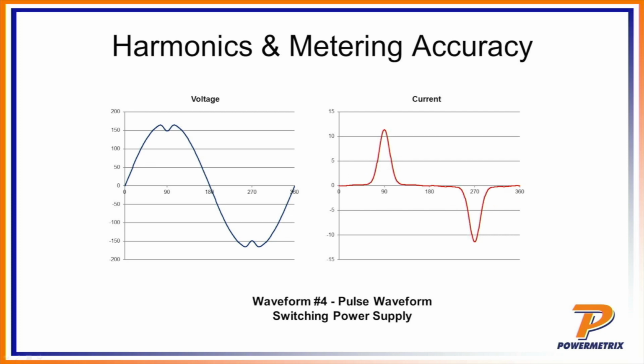Fourth waveform is yet another example of a switching power supply called the pulse waveform. Once again, you have a sinusoidal voltage, big current spike on each peak and trough of every sine wave. Once again, you see, even more pronounced on this, the little inflection that's being caused because of that current surge. And that's each and every cycle. That will not go away until you either change the load or filter the load in some way to be able to get rid of that.